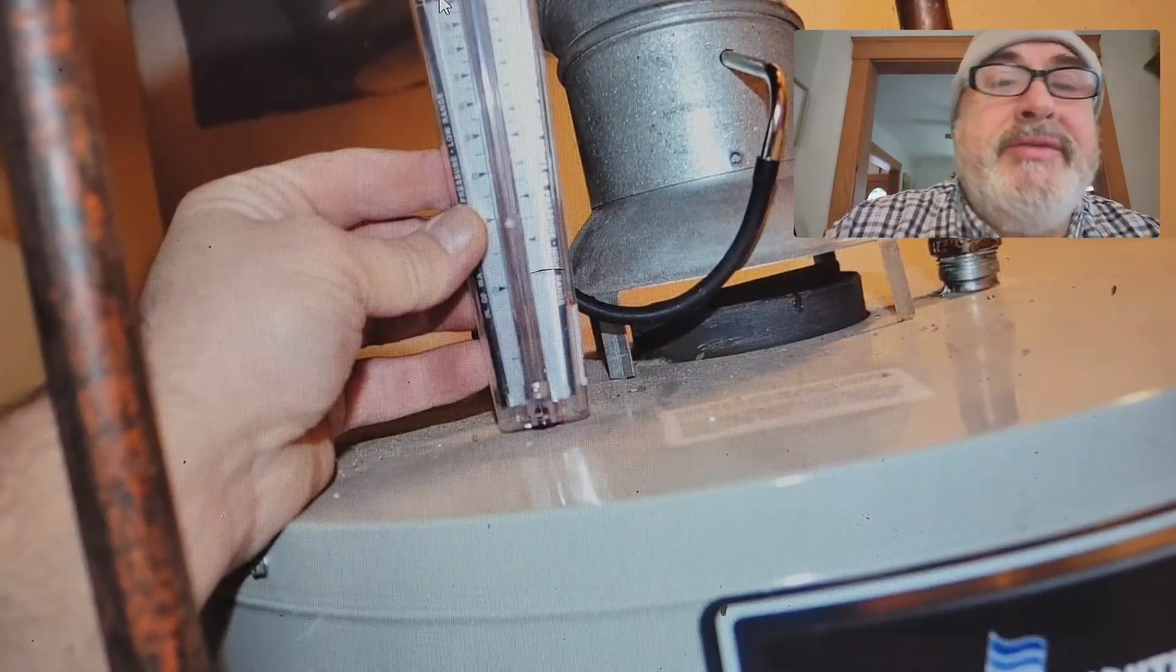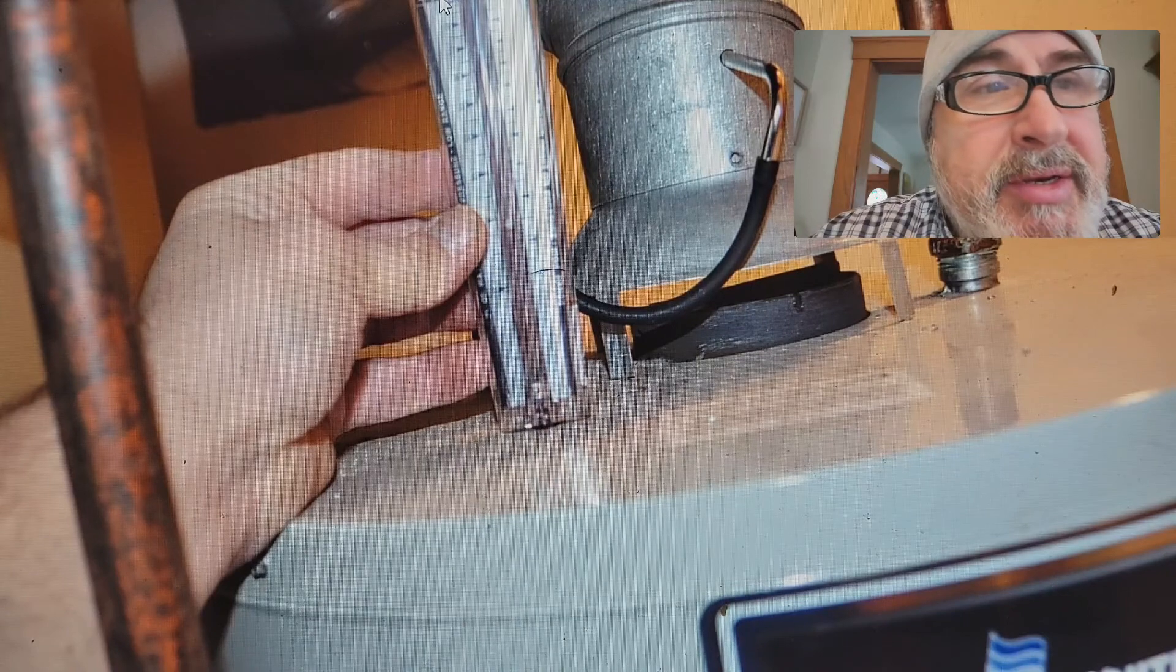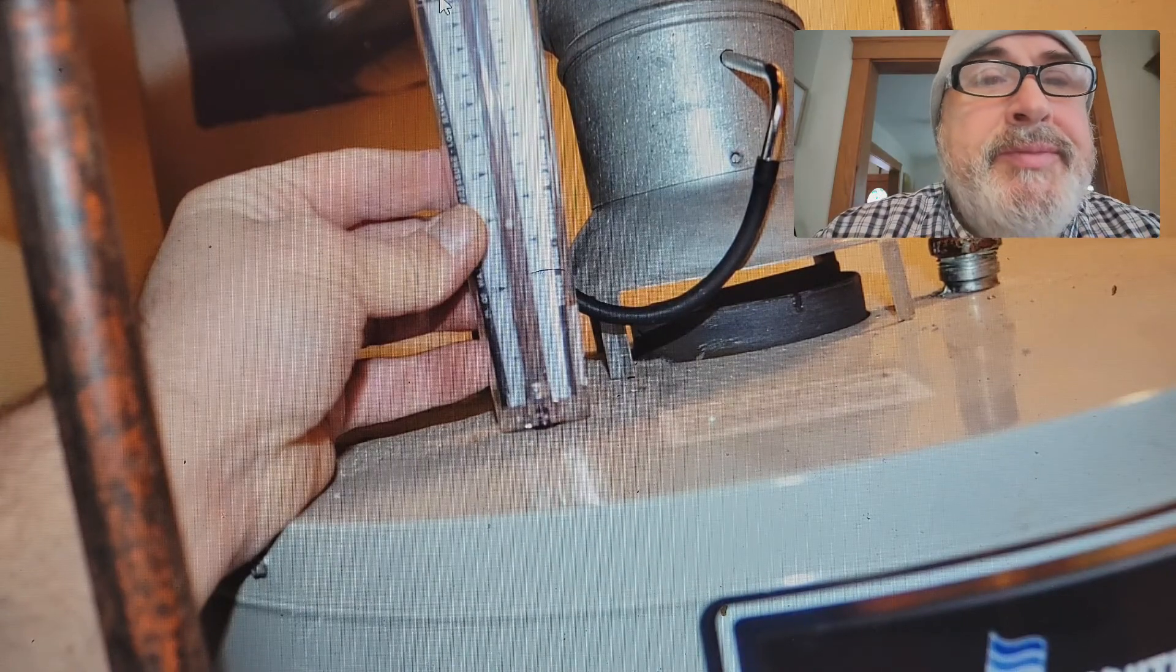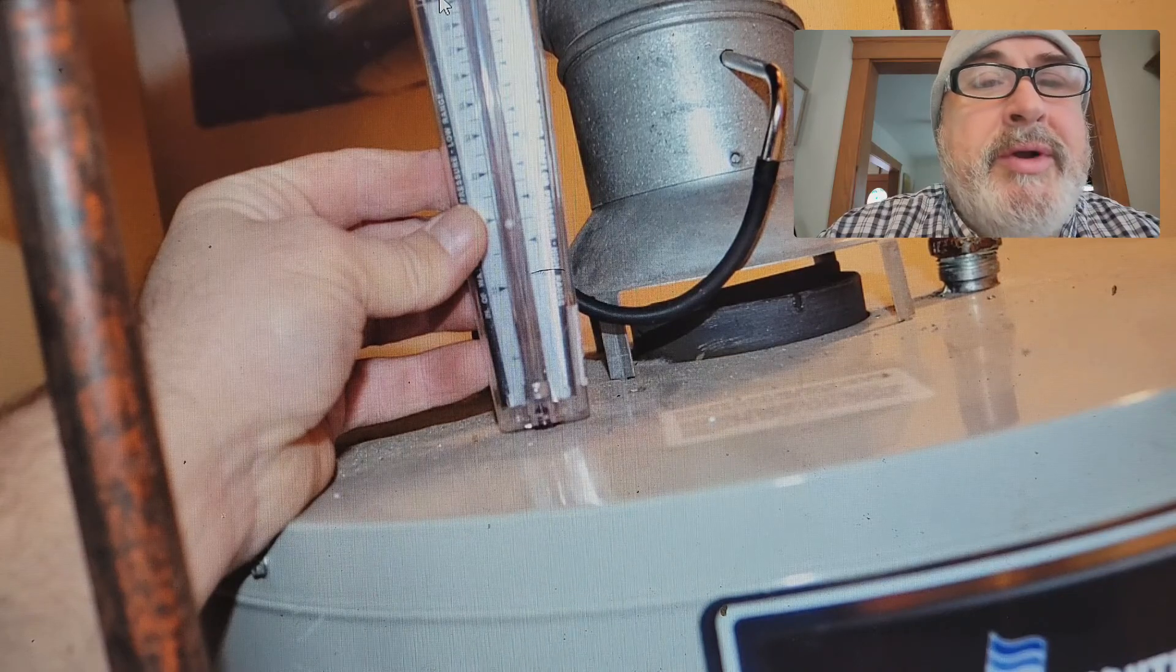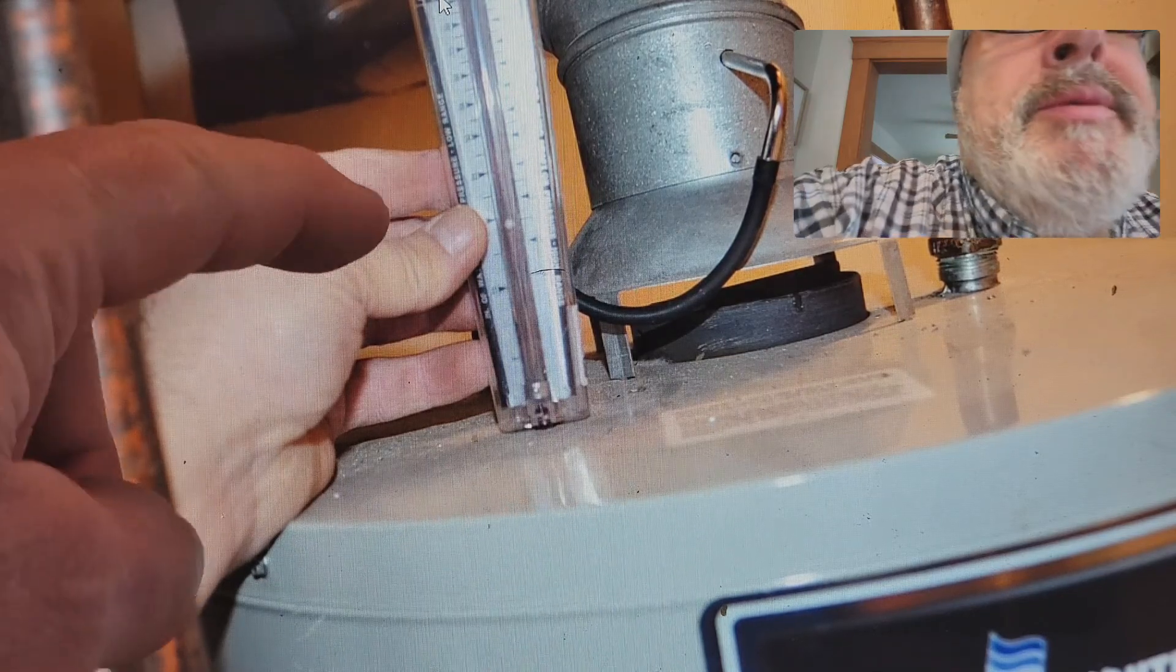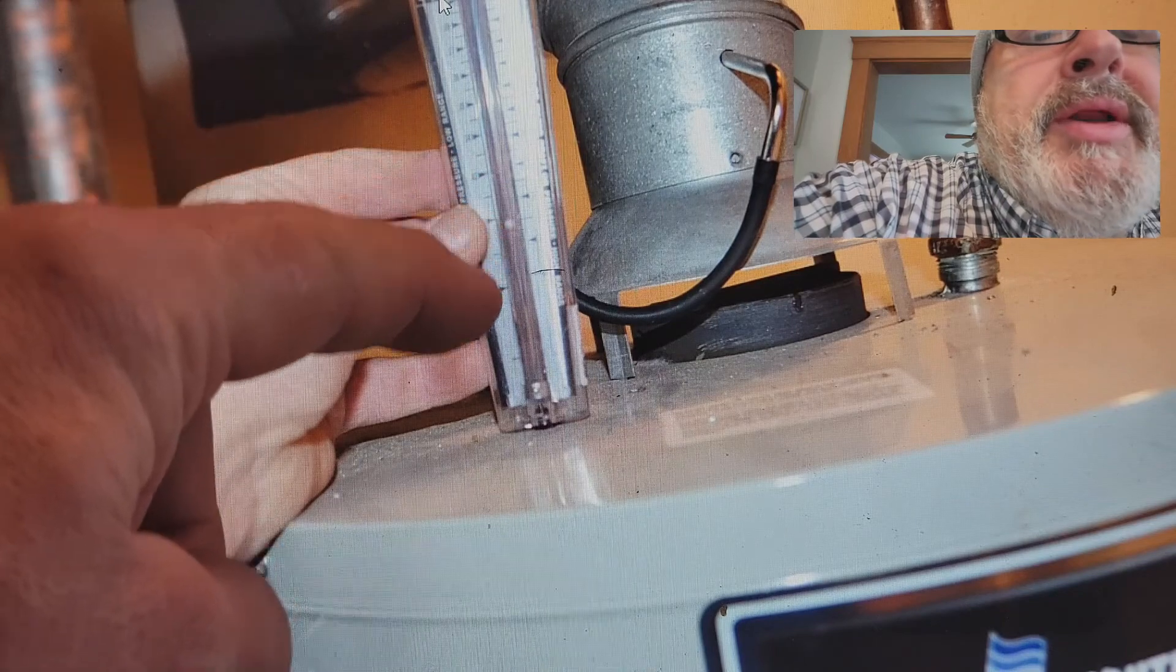So here's a draft test. So here's why you need to know your draft. So basically you drill a hole in the flue. And this is called the Dwyer's draft gauge. And you can see the little ball is right there. And that's where you want it between these two.